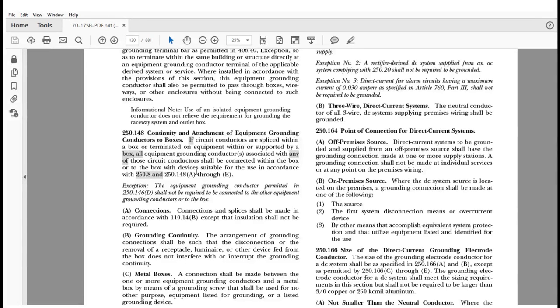It's also reminding us that there are some provisions where you don't need to do that, where you have isolated grounds. It still gives you that leeway in the exception, okay? It still gives you those leeways in 250.146(D) where they're isolated pieces of equipment. We get that. It's all still there. We understand some of the direction there for the isolated ground circuits and for existing applications. But the real intent here was to remind you that we need to make all these connections together. And that was the intent here that had to take place.